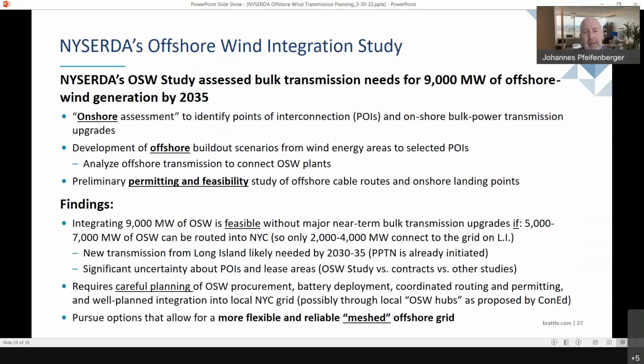The study found that if you carefully select the interconnection points by choosing the most robust and reachable points on the onshore grid, integrating 9,000 megawatts into the New York grid is feasible without major near-term bulk transmission upgrades beyond what the state already has under development. It would, however, require that 5,000 to 7,000 megawatts of that 9,000 megawatts would be routed into New York City. So only about 2,000 to 4,000 megawatts would need to connect to Long Island.